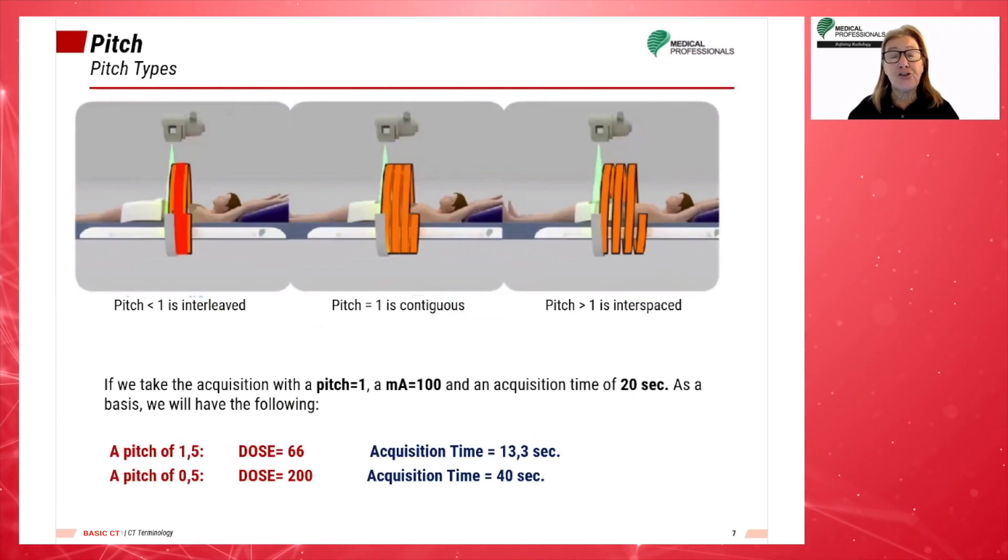As shown in this slide, higher pitch reduces image quality and patient dose, while lower pitch increases image quality but increases patient dose. For example, the image quality for a pitch of 0.5 is improved but the patient dose is abnormally increased.